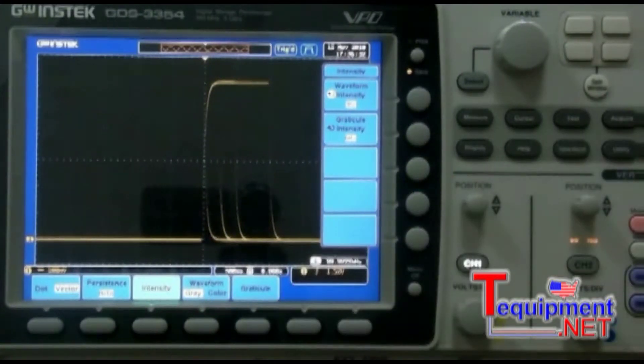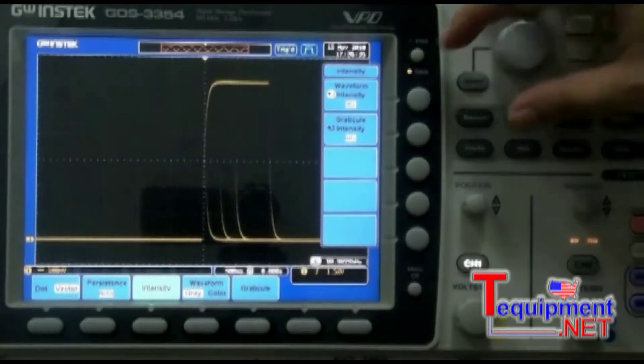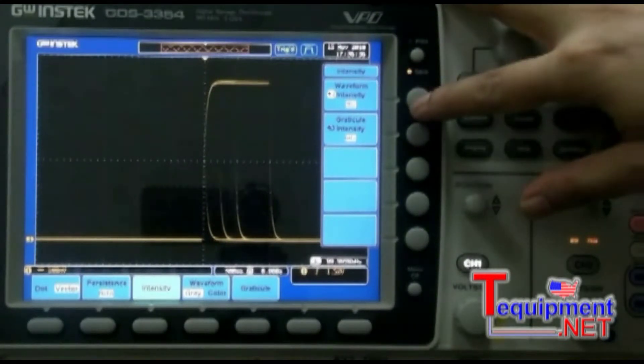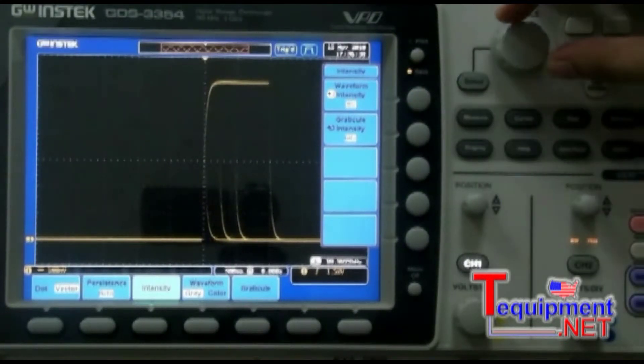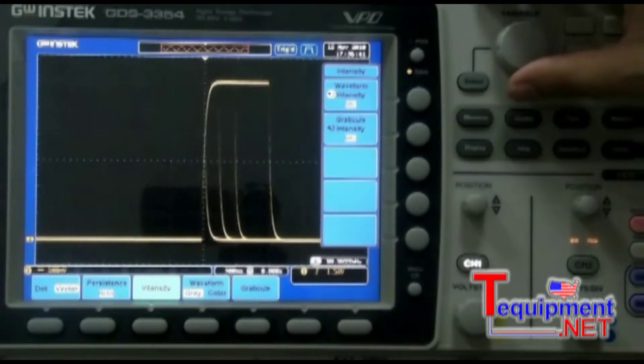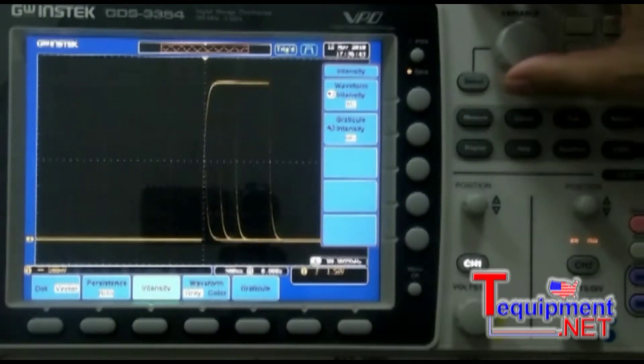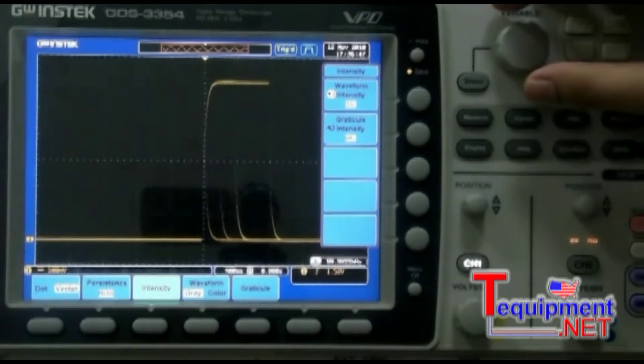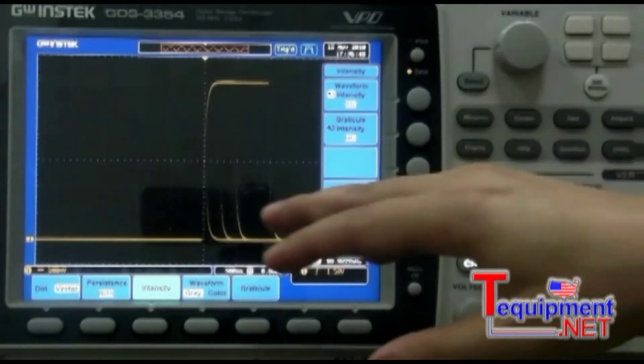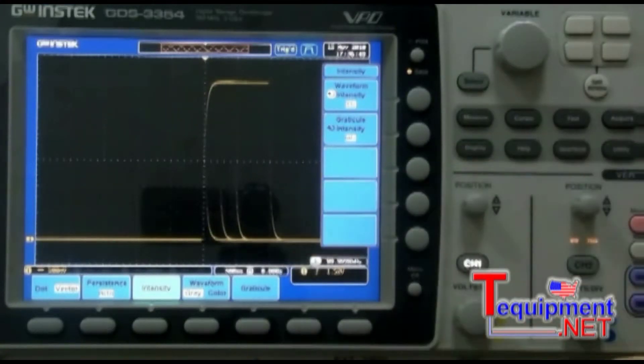Toggle the waveform gray or color icon back to gray. Press the intensity key on the bottom menu and use the variable knob to adjust the intensity. This demonstrates how a surge waveform looks similar on the GDS 3000 and on an analog oscilloscope with similar levels of luminance.